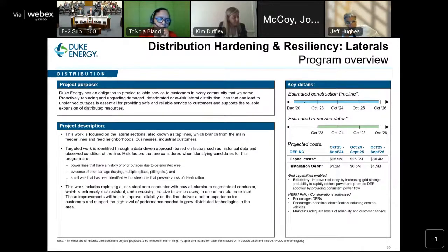What we most commonly find with this program that needs to be addressed is an older vintage steel core wire. It was a high strength wire, an older vintage of material, that gave us high strength, but over time that steel core providing the strength presents a corrosion risk. And as that corrosion risk increases, there's potential for failure in those particular cases.